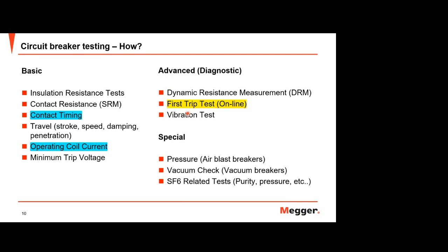So the first trip is also referred to as standard testing to analyze your circuit breaker. And the good thing about the first trip test is that you can also get some measurements, some parameters that you normally get with the basic testing, like the contact timing and operating coil current. This can also be seen by first trip testing.